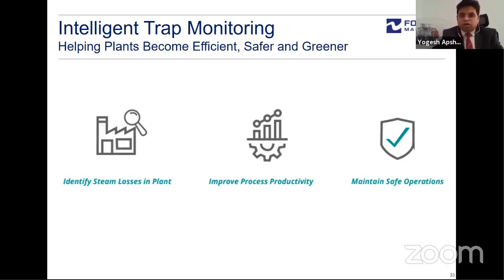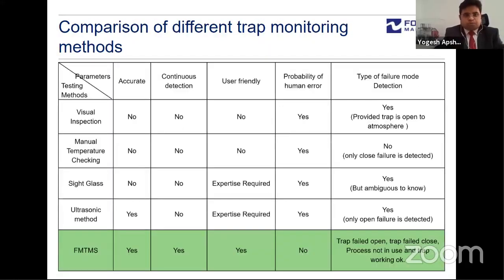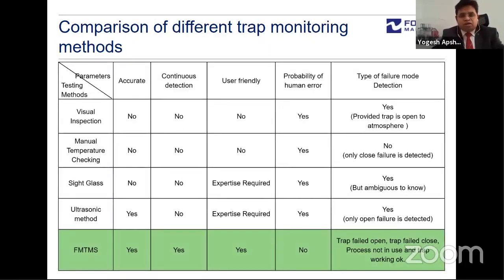So it is very important to identify whether the steam traps are working or not working, which will directly impact your uptime of the equipment, the batch timings and the steam consumption, and at the end, your gas consumption or your fuel bills. So what do we do in trap monitoring systems? If you compare the different types of trap monitoring methods, today the majority of the pharma industry is doing visual inspection with the sight glasses, or visual inspection by opening the bypasses, then manual temperature checking of the steam traps, and the ultrasonic method.